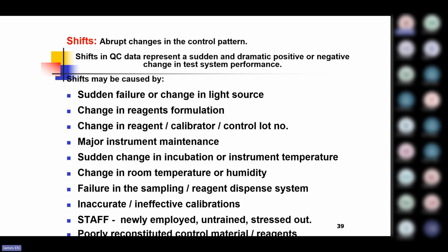That's why after major maintenance, you should recalibrate all parameters. Don't just run and say you are trying to save cost. You are interested in patient safety. Please take your time and recalibrate all parameters. It won't cost you anything.